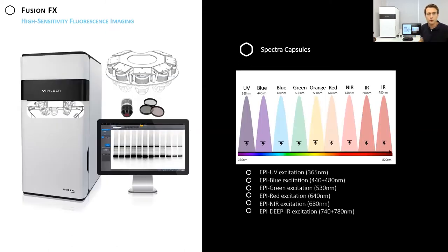And what is fantastic with this capsule concept is that you can customize your own system and configure the instrument in a way to meet your imaging needs. So it means that inside you have a capsule holder that can welcome up to 7 fluorescent capsules for multiplexing capabilities and fluorescence applications. And we offer a range of 9 capsules. So you have available capsules from UV, blue, green, orange, red, near infrared, down to deep infrared.